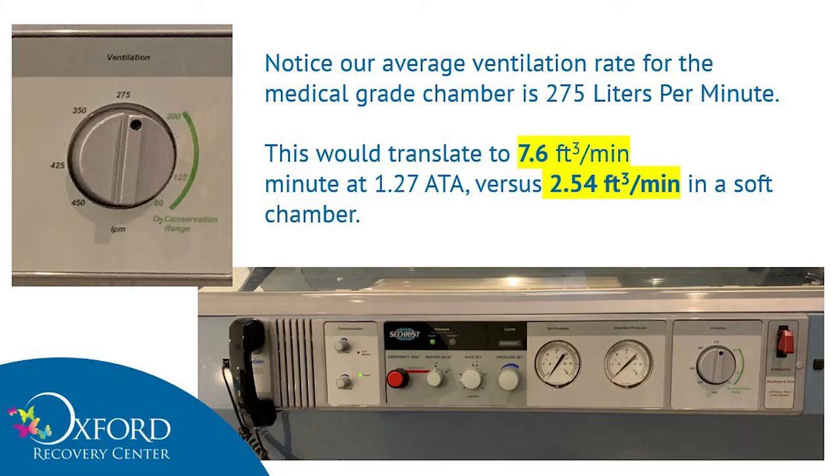Let's contrast this to our chambers. Typically, we ventilate at 275 liters per minute — that's pretty much a minimum. Some people, if they're a little bigger, will go up to 350 or higher. If we were giving that kind of ventilation in the mild chamber, we'd be giving 7.6 cubic feet of ventilation as opposed to 2.54. So basically, at our minimum, we are way over the standard.